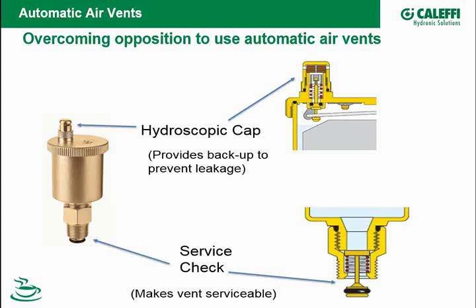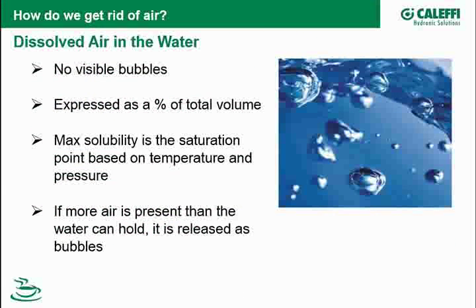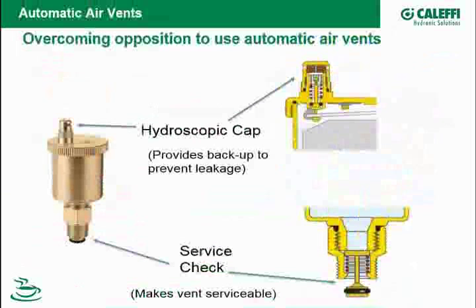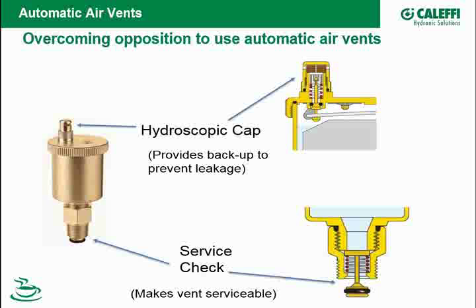Personally, I think most systems out there still need automatic air vents because of the way technology has gone. We do make an adapter for the top of that air vent if you want to put a copper tube on it and take it down to the floor or down to a drain. One excellent entry from last month had little copper tubes connected to every one of his air vents on top of the boiler — knowing that someday it could leak, putting a little copper tube down to the floor or a drain would make you sleep better at night.